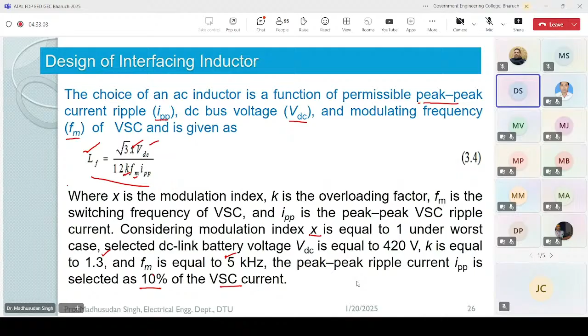Usually if operating at a modulating frequency around 5 kilohertz, the safety factor considered is 30%, so 1.3 K. We allow peak to peak ripple around 10% of the VSC output current. At the given DC link voltage, the worst case modulation index X can be considered as 1. With these values, you can find out LF.